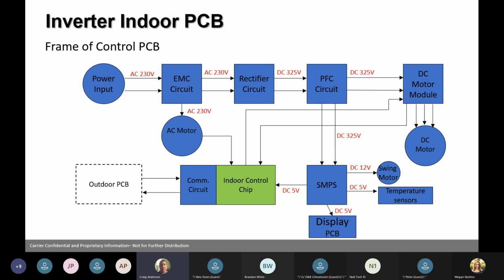So if you're getting erratic operation, some days it works and some days it doesn't, monitor the electrical power going to the unit. Put your amp probe on it, let the unit run, and see what the voltage is doing. Don't just check the voltage and take it off. Let's see what it's doing while the unit is running.